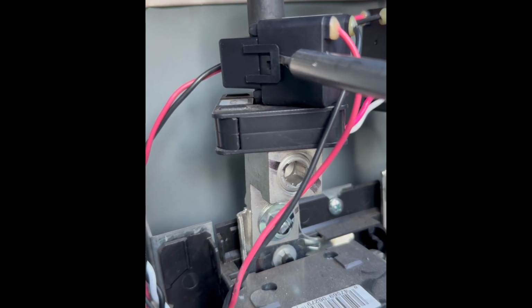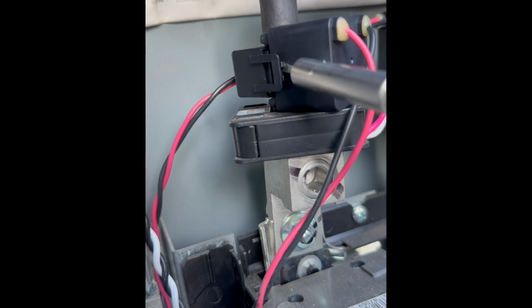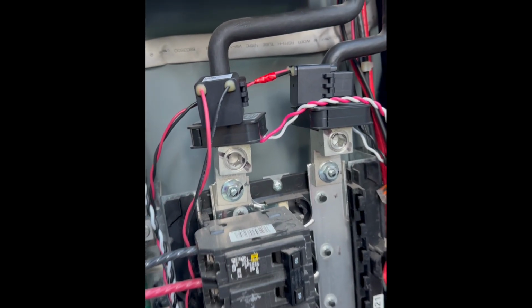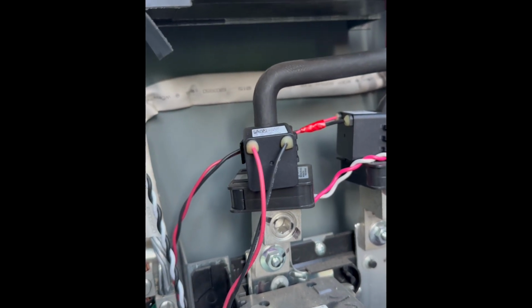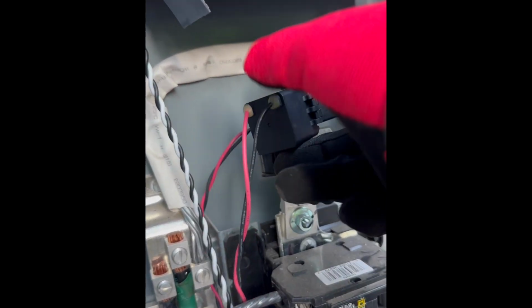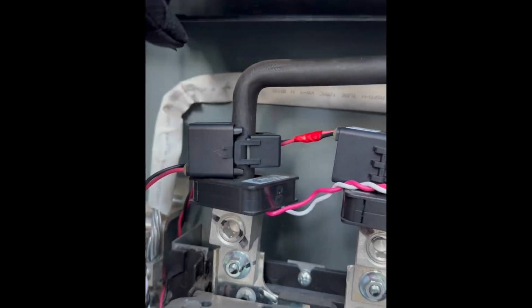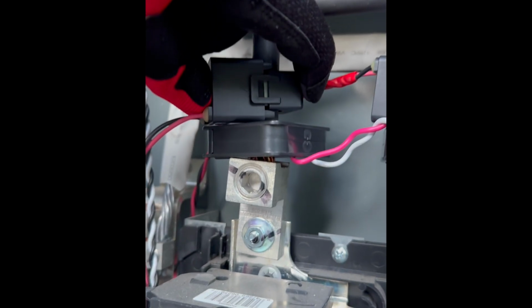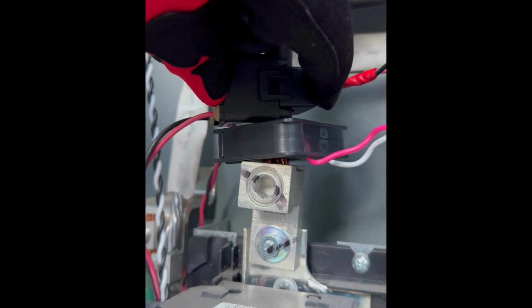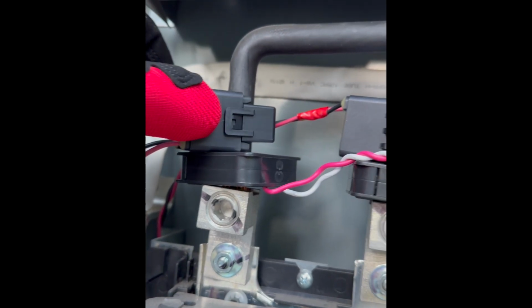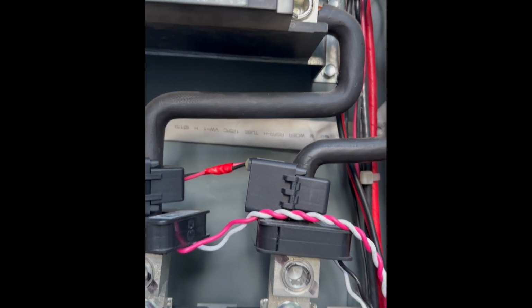Alright, so we're just gonna flip these guys over and see if that fixes things. Again, it turns out that physically flipping these CTs is unnecessary because there's a way to virtually flip these in software. I didn't know that yet, and don't worry, I'll describe that soon, but for now, I was doing it the hard way. It's worth noting that flipping these goes against the label on the CT that says it should face the power source, but online forums indicated that at one point there was a batch of CTs that got labels put on the wrong side, so I was thinking that maybe that might have been the problem. I'm gonna set down the camera to flip the second one.